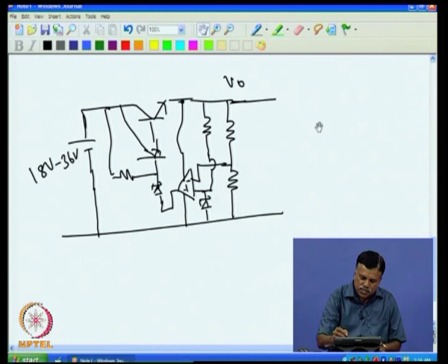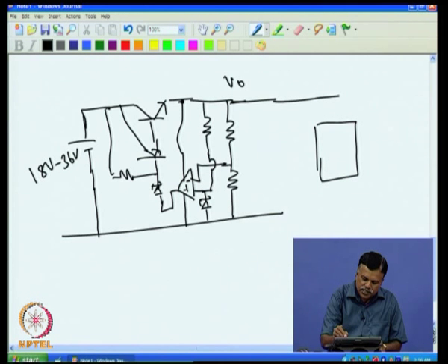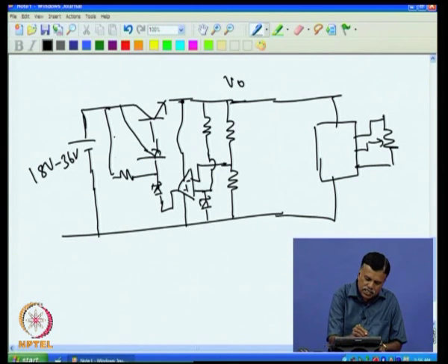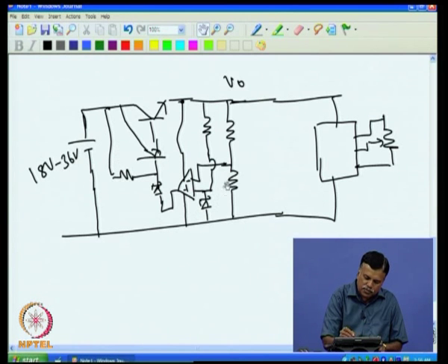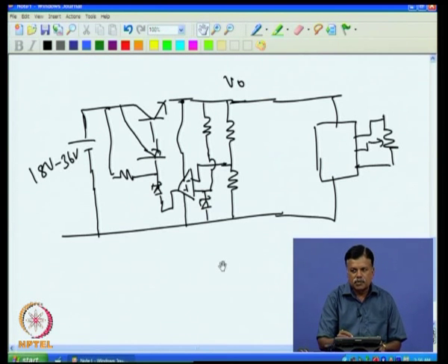I will show you this. What you do is, in the actual case, we will put a current transmitter here. That will be powered by this regulated voltage. Then we will have our potentiometer connected here. When the position varies, the current drawn by this varies, and so does the current that is coming from here. So, the total current that is going will be the current consumed by this, and the current consumed by this, plus the current driven due to this. So, we have first the voltage regulator part, then we have the current transmitter part. First let us concentrate on the voltage regulator part, then we come to the current transmitter part.